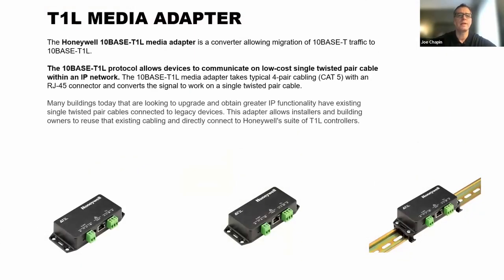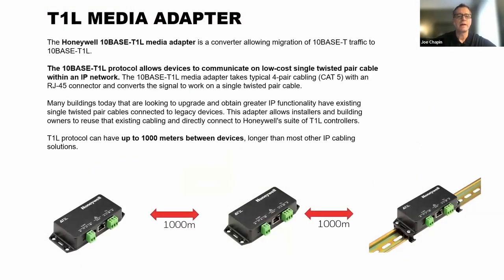This is the T1L media adapter. This will allow you to extend it 1,000 meters between devices. So if it's a lot of facilities, I know sometimes they have an outbuilding that they want to get connectivity to, and they have a long 2-wire circuit. This is how you do it. So if you can't go 300 meters between the controllers, you can go up to 1,000 meters with this device here. So this, again, either Cat5 or T1L twisted pair.